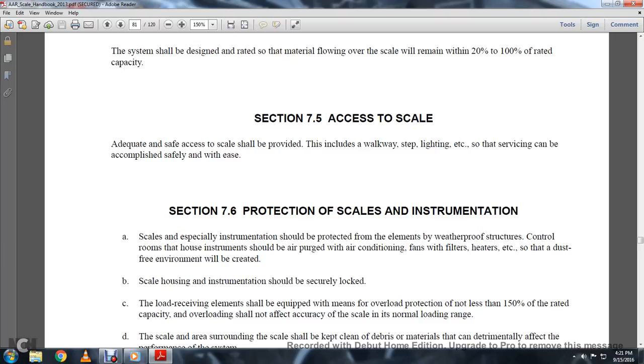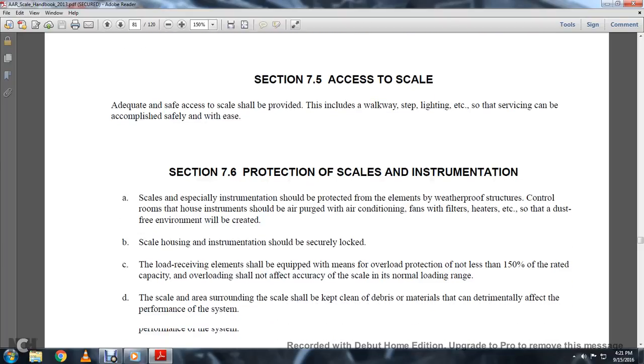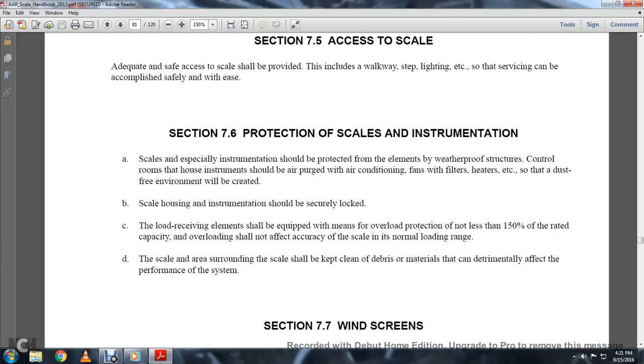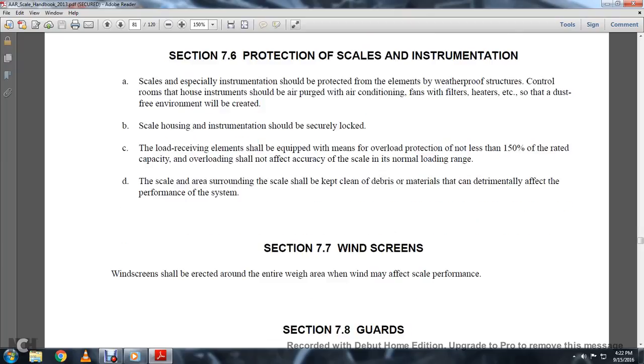Section 7.6, Protection. Scale instruments should be especially protected with elements: waterproof, weatherproof, control room, instrument, air purge connection, fan filters, and heaters, so that a dust-free environment will be created. Scale housing instruments should be secured. The load-receiving elements should be equipped with means of overload protection of not less than 150% of rated capacity. Overloading should not affect the accuracy of the scale within its normal loading range. The scale area should be kept clean and free of debris and material detrimental to the performance of the system.